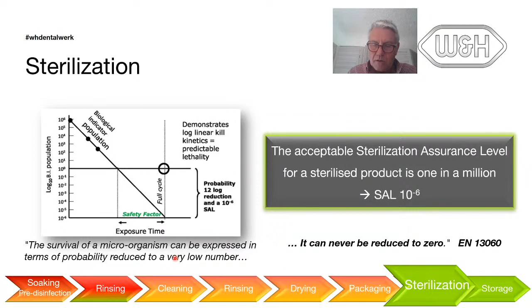This is a bit technical. It shows you initial contamination. This is when you take your instruments from the chair: 6-log contamination. The first disinfection will drastically reduce the amount of microorganisms, so it participates a lot in the success of sterilization indirectly. So we talk about a reduction of 10 to the minus 5 log. Then you clean. By cleaning, it's another 2 or 3 log. You divide the microbial population by 100 or 1,000. And then 10 to the minus 6. This is the last step provided by the sterilizer. And here, inshallah, we have 1 in a million. Yes, this is the theory. So do not underestimate, please, this pre-disinfection and cleaning phase. Very crucial. Of course, autoclaving is also very crucial.